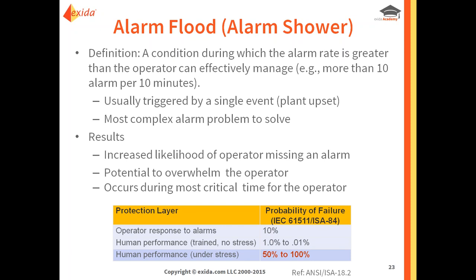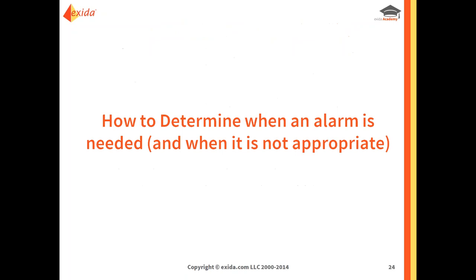During a burst after an unplanned event — what we call an alarm flood — the standards recommend no more than ten alarms in a ten-minute period, or else the operator becomes overwhelmed. When operators are overwhelmed, the likelihood of responding incorrectly, not responding in time, or missing the alarm goes up dramatically in that stressful upset scenario. That is one of the main reasons why we want to prevent alarm floods.